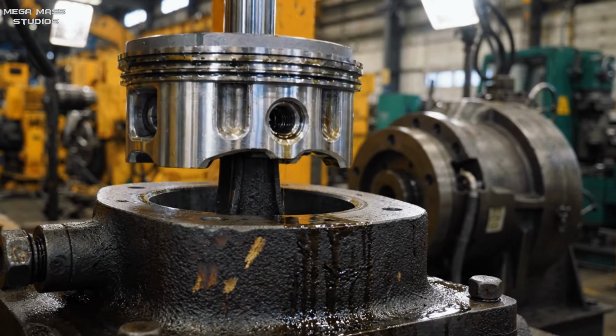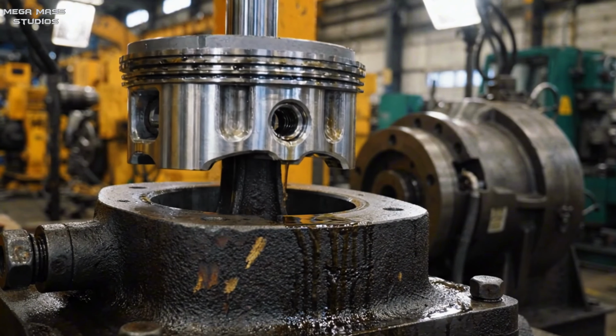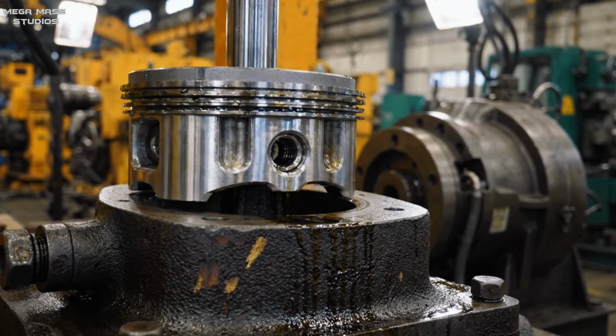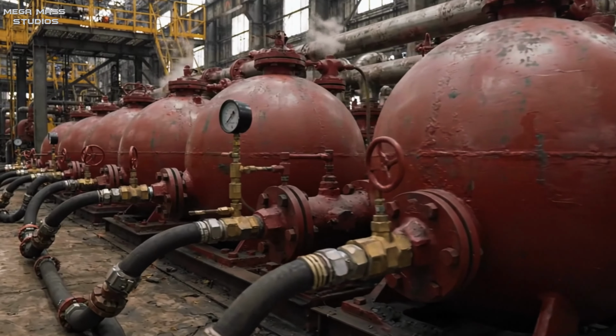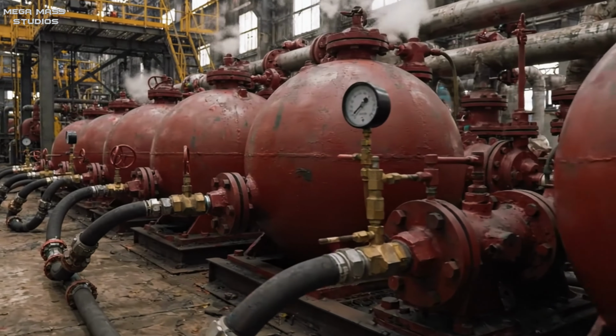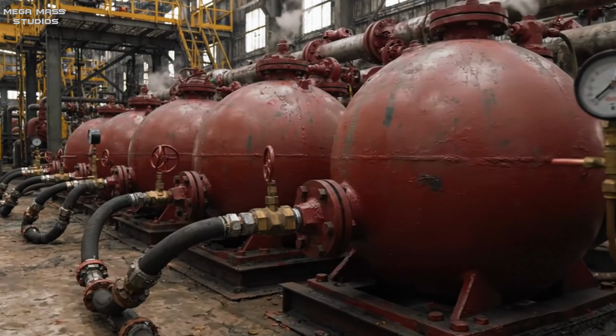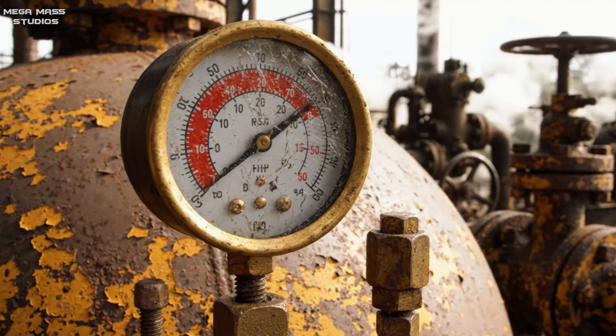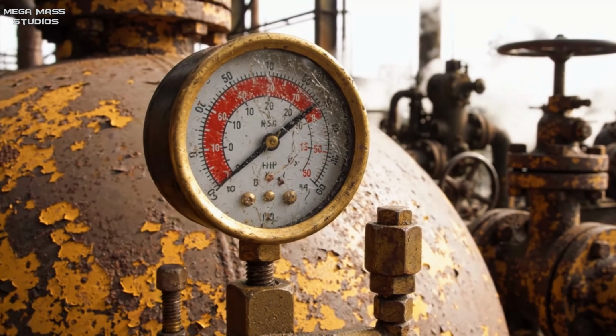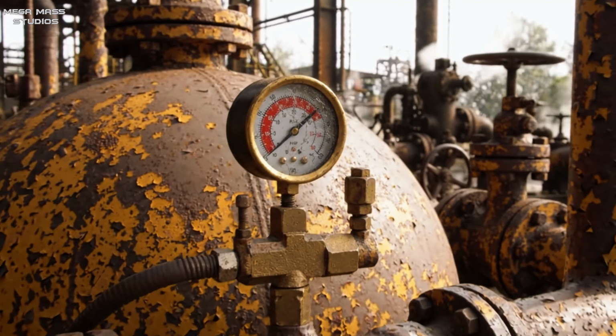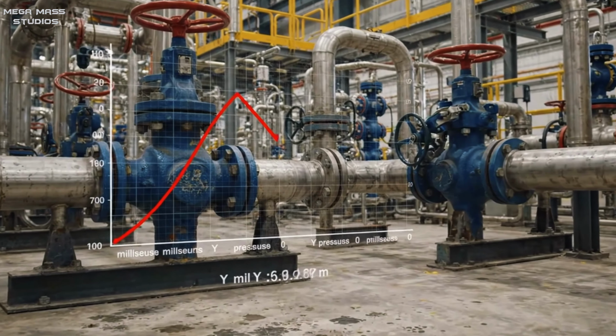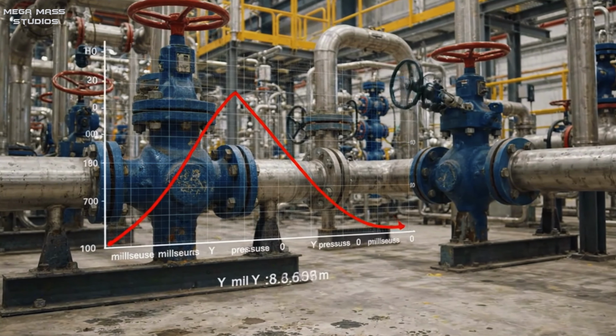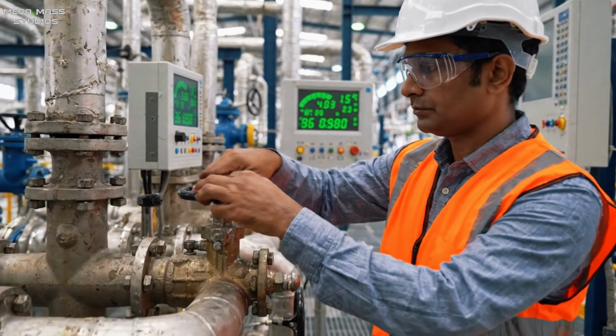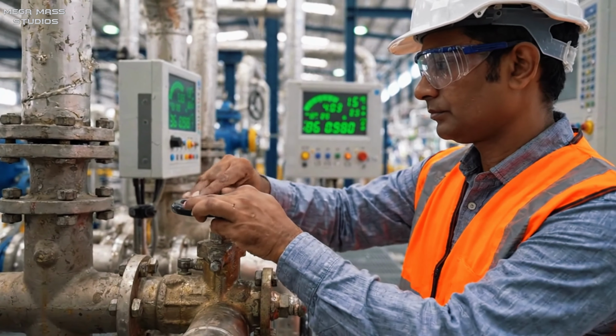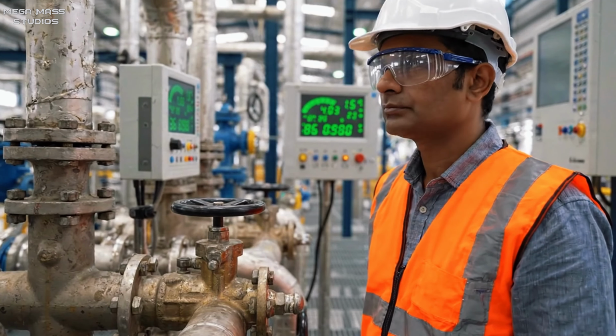To close against a high-velocity water column, the valve pistons must exert over 300 metric tons of force. This extreme closing force is generated by dedicated high-pressure nitrogen gas-charged hydraulic accumulators. These heavy steel spheres store massive potential energy, ready to be released in less than half a second. To prevent a catastrophic water hammer effect during rapid closure, the valve speed is digitally regulated. The deceleration curve follows a precise multi-stage profile, slowing the final closure to dissipate pressure surges.